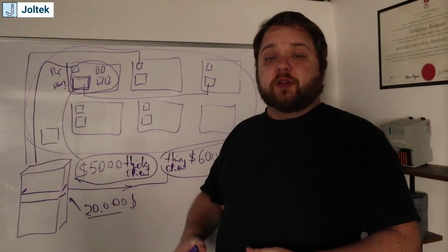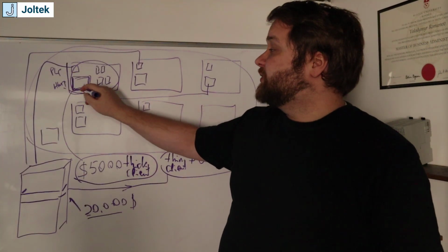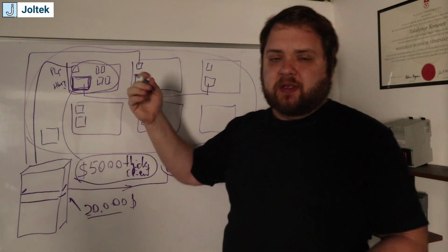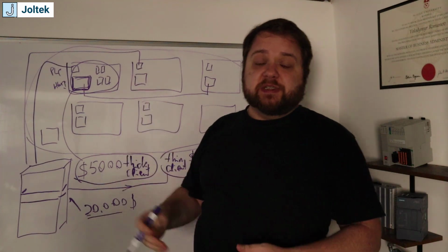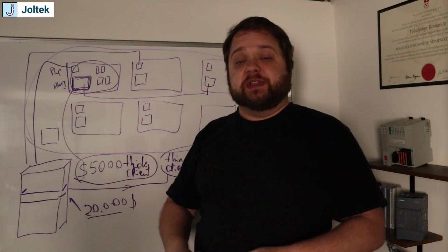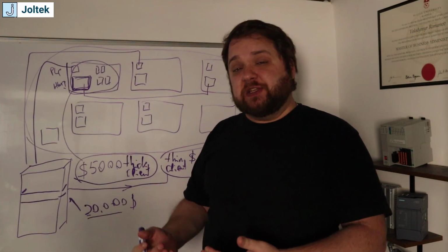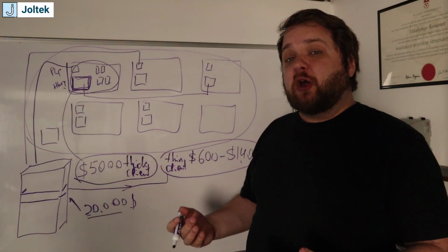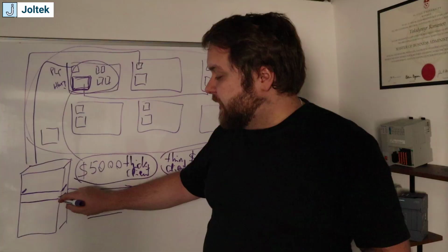So if you have worked on the Rockwell side, you have your FactoryTalk View ME terminals, and those are going to be standalone. Depending on whether you select a performance version, you can connect to multiple PLCs. If you select a standard one, you can only connect to a single PLC. But as you scale that into FactoryTalk View SE or Site Edition, you now have the capability of hosting the entire application on a server.